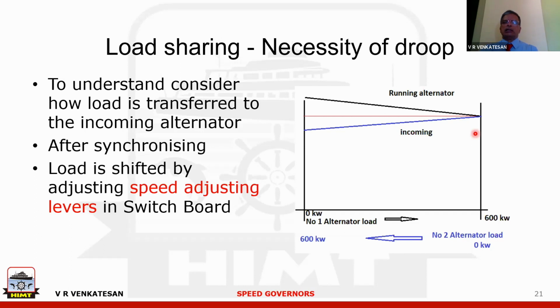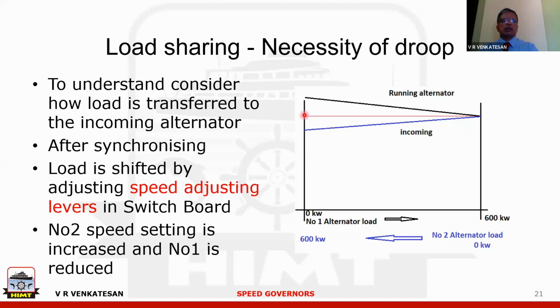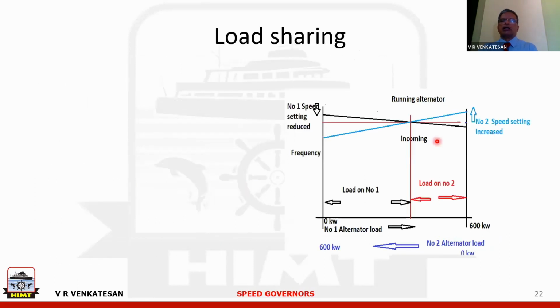That means you are changing the set point of the incoming generator's governor. That means this blue line will move up. You are actually moving this point. The blue line will move up. And what do you do to the other generator, the running generator? You will move down. Reduce. That means this point is brought down. So what happens is number 2 setting is increased and number 1 setting is reduced, and you get an intersecting point like this.